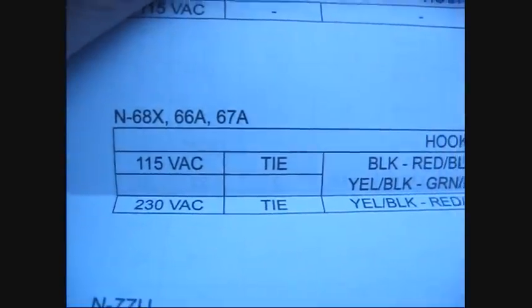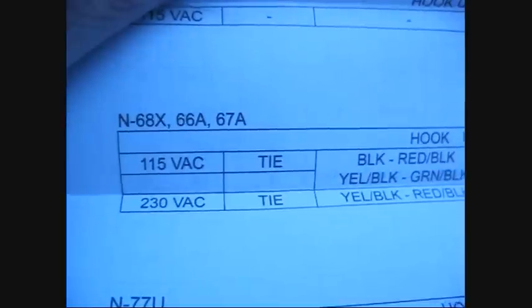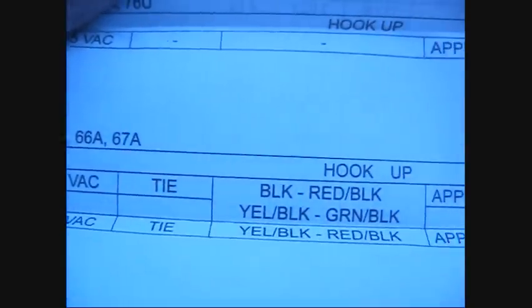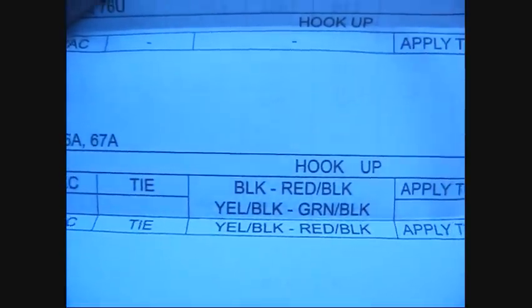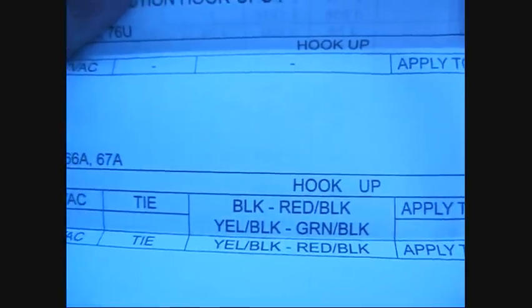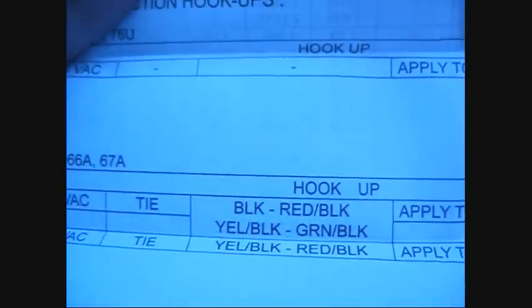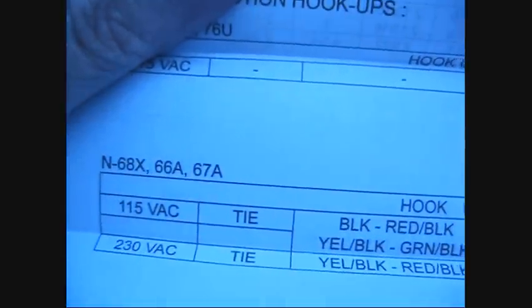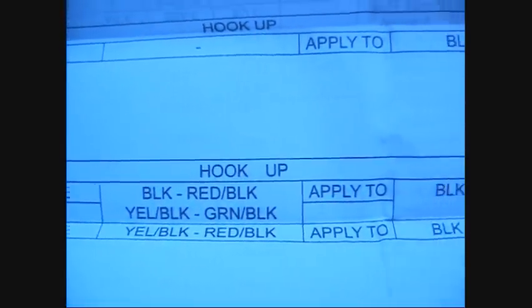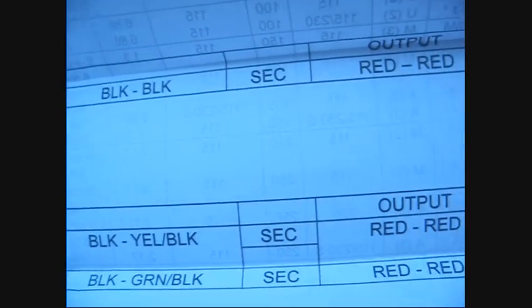This is an N68X, which has a dual voltage primary, either 115 volts or 230 volts. For use with 115, we tie the black and the red-black together, and the yellow-black and the green-black together. If we were using 230, we would tie the yellow-black and red-black together and apply our incoming AC to the black and green-black. For 115 we'd apply the incoming AC to yellow and black, and then of course red as our secondary.